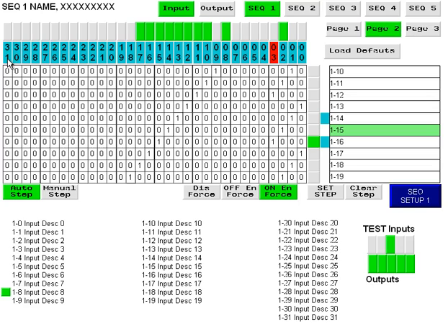troubleshooting on a sequence. For this demonstration, passwords for the row of buttons below the matrix have already been entered. Configuration and status are available to the operator, in-house maintenance, and the PLC programmer through the HMI.